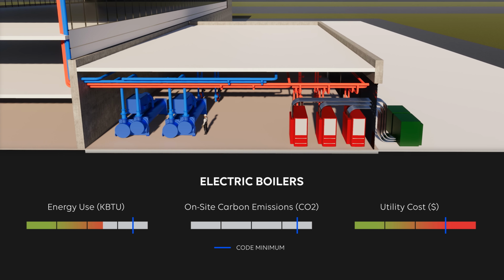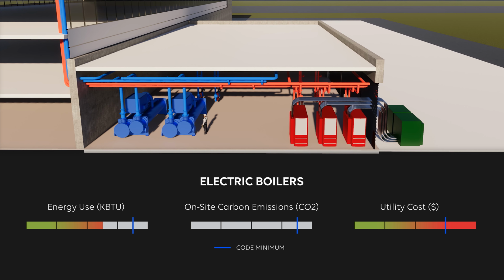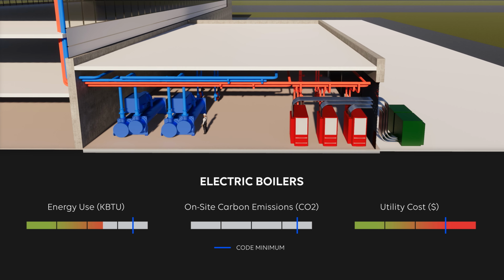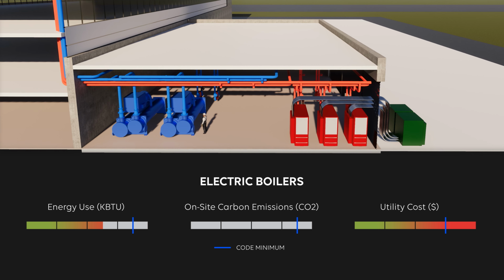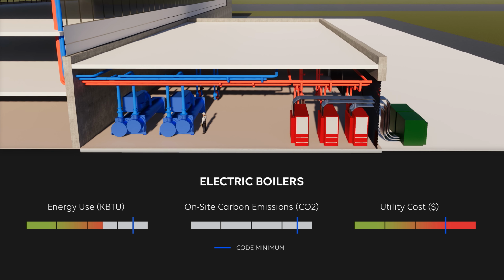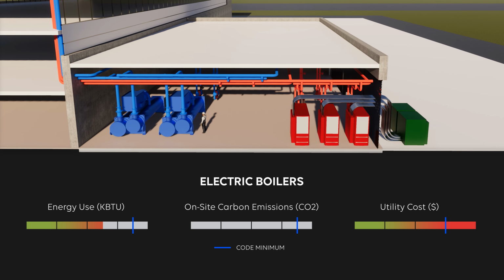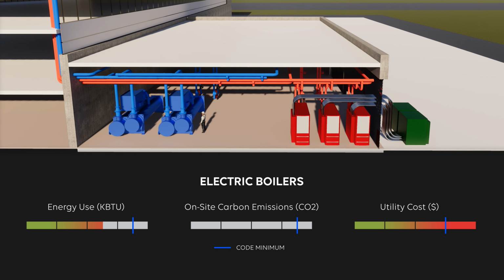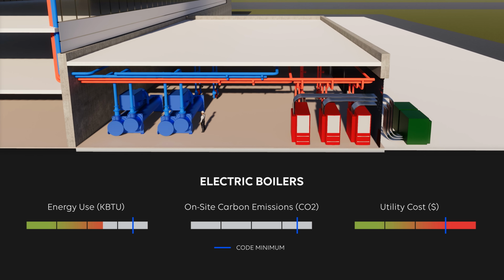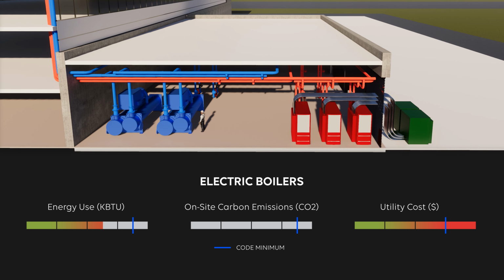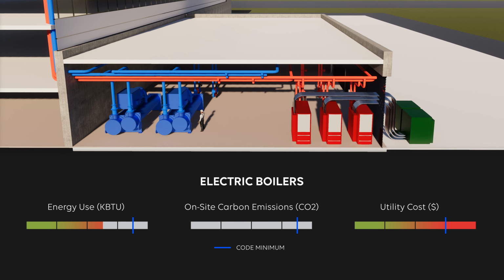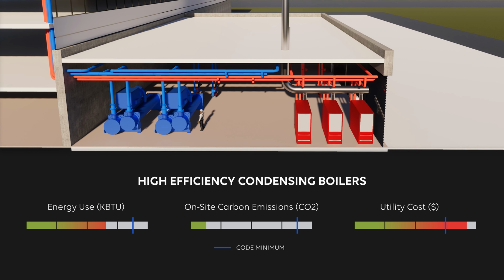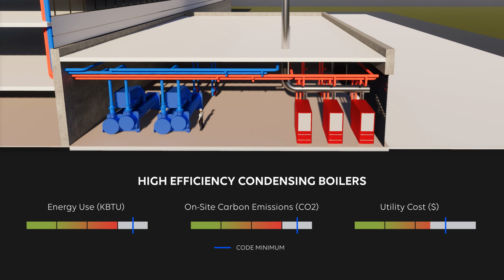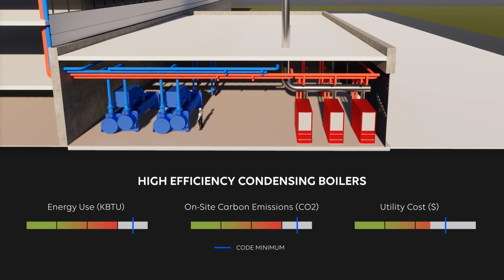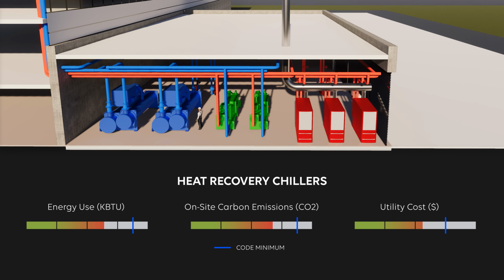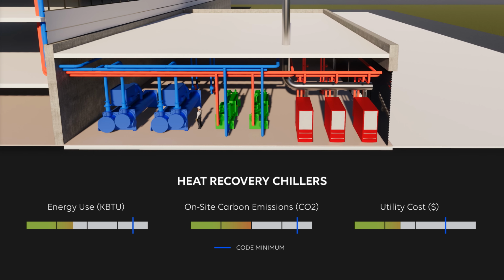This does increase efficiency, but typically the utility costs increase too. While on-site emissions are zero, there are Scope 2 or grid emissions, which vary throughout the country. Utility companies are working to reduce their carbon footprint, but at this time, an electric boiler usually has higher total emissions compared to a condensing boiler. For the rest of the video, high-efficiency condensing boilers will be the baseline in the graphs. A good supplement to boilers are heat recovery chillers, which have efficiencies far greater than an electric boiler.